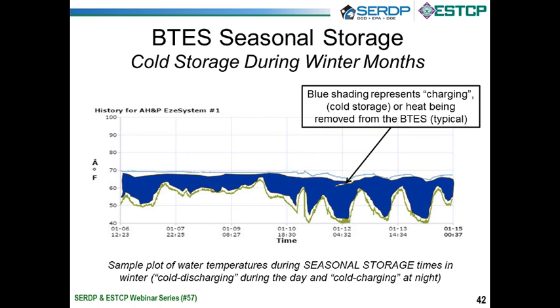Now this is January of 2015. We're making cold all night long, all day long. So from the 6th through the 15th, 9 days, we did pure cold storage. And as you can see, we got the water down to 40 degrees heading out to the Betis. So we can chill that 7-degree limestone pretty good with 40-degree water.